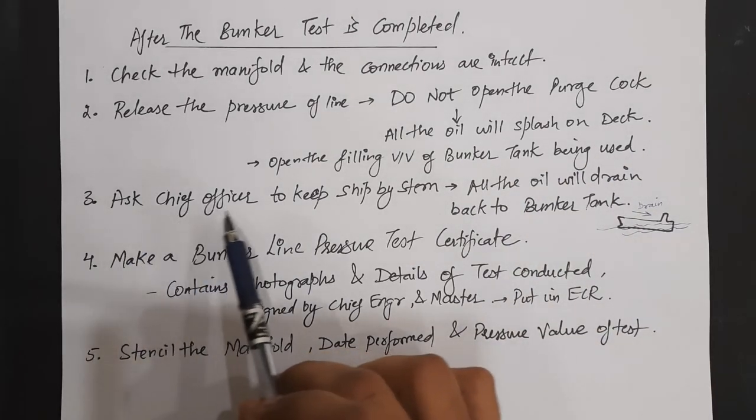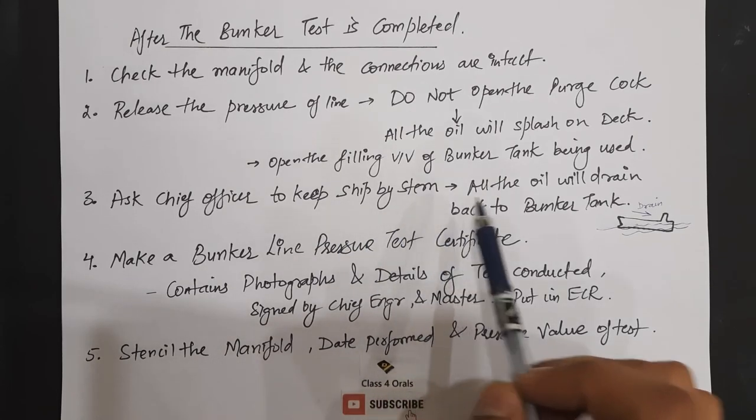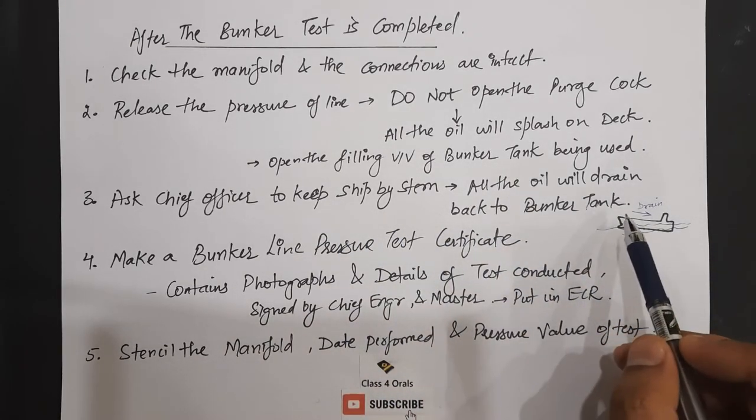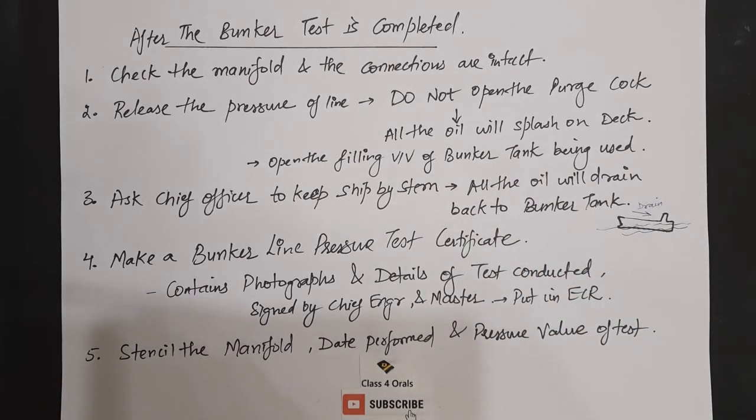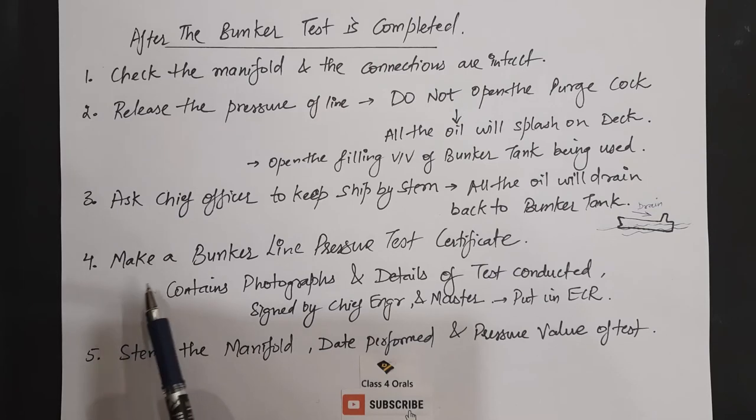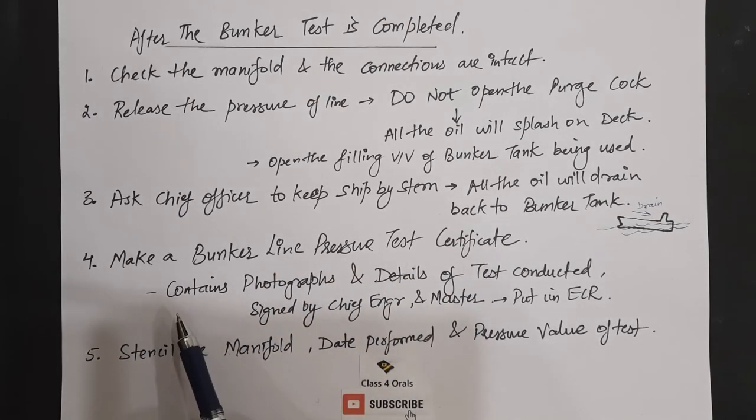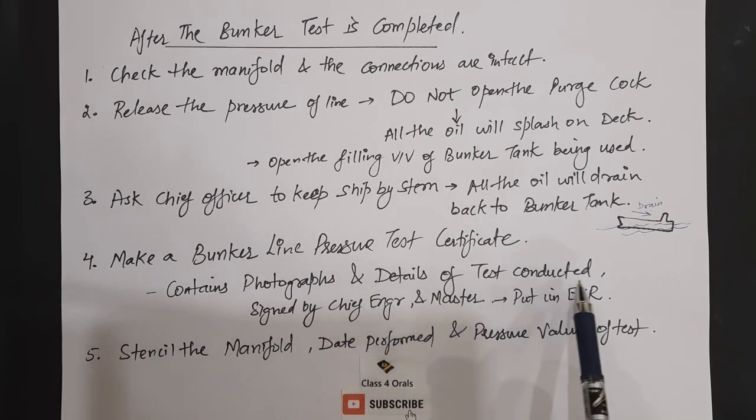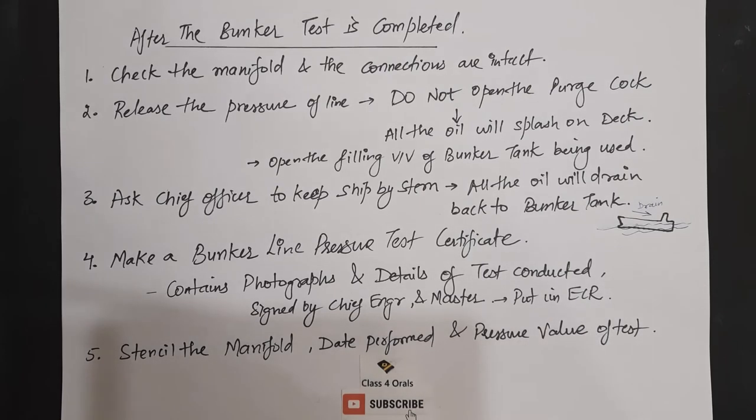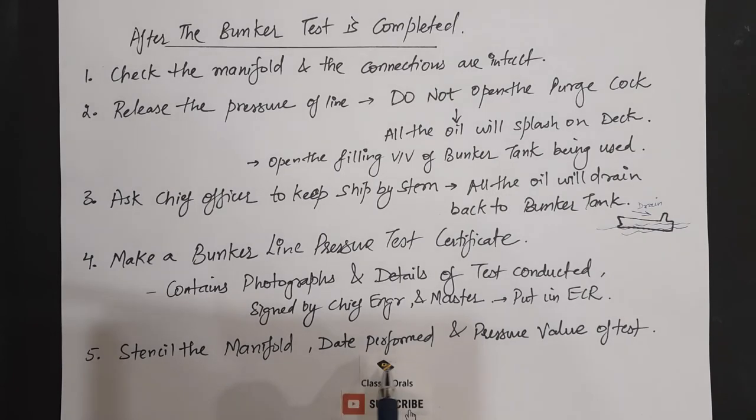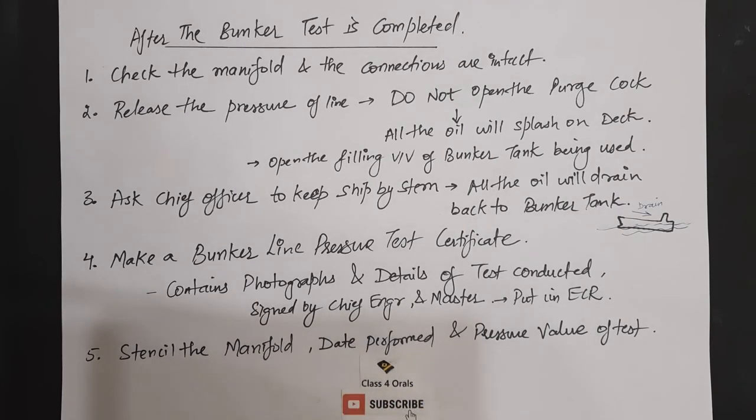Open the filling valve of the bunker tank being used. And ask the chief officer to keep the ship by stern. Because if you keep the ship by stern, then by gravity, all the oil will drain back to the bunker tank. And it will not cause any kind of headache to the emptying of the bunker line. Make a bunker line pressure test certificate which will include the photographs and the details of the test being conducted. And counter sign by the chief engineer and master and put that certificate in the ECR. And stencil the manifold with the date performed and the pressure value of the bunker line pressure test.